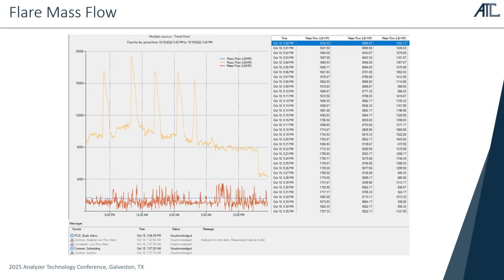This is an example of the trend. Once all the SO2 values are calculated, in this case for 3 different flare emissions, the values can also be trended, and various alarms, which you can see at the bottom, though it's probably too small to see, are generated based on these regulatory parameters.